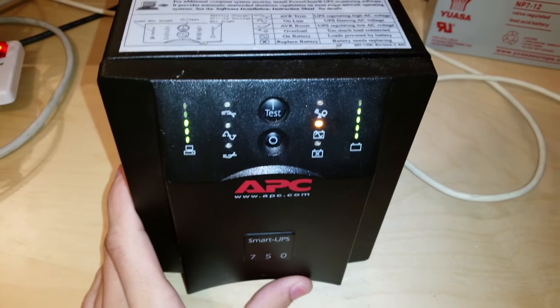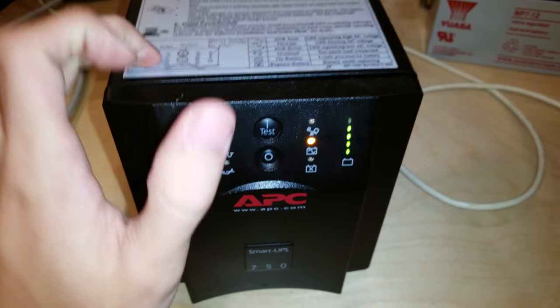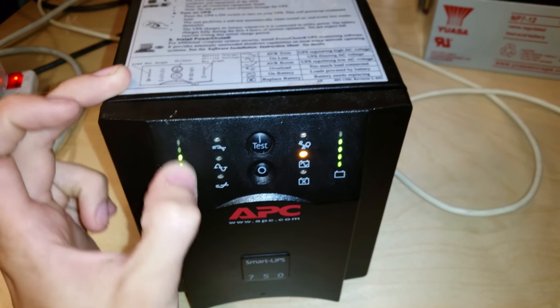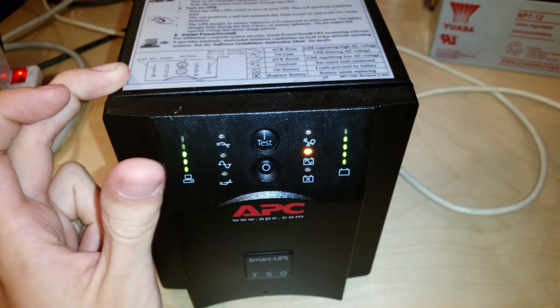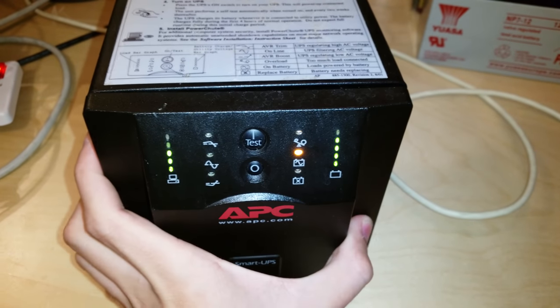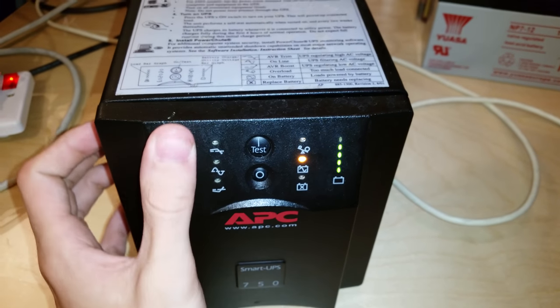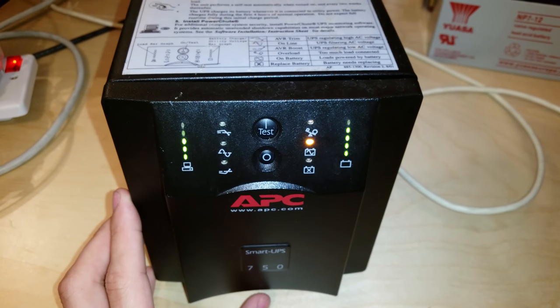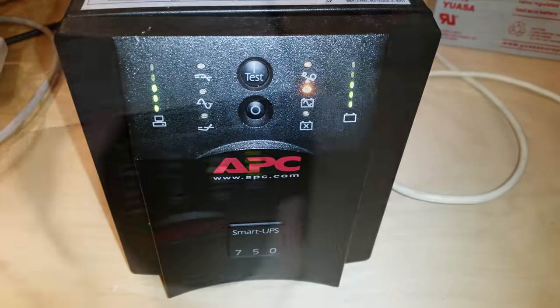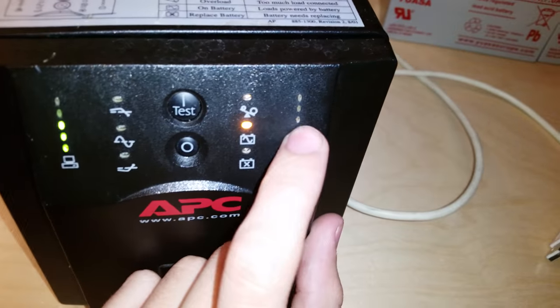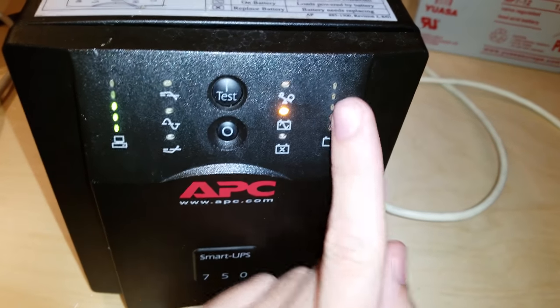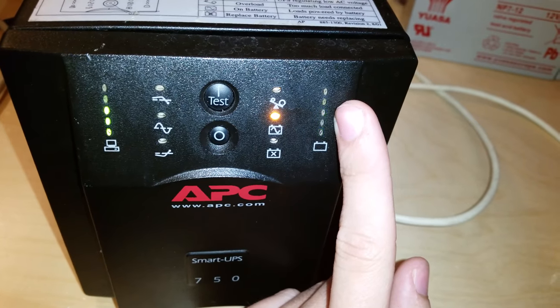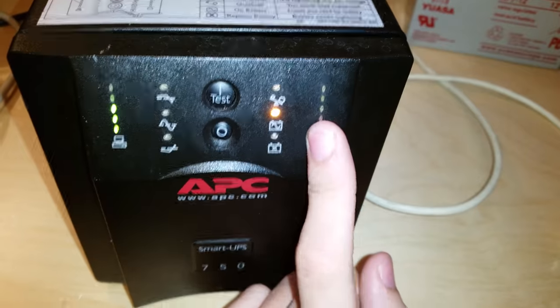That's the basic rundown of it. You just run the batteries completely flat so that then records how long it managed to run for this load that it's under now with like 60-ish percent. It's probably not going to be at that load all the time. The chances are the average load on this thing is going to be around about 40 to 50 percent, but it may hit as high as 60, which is why I'm calibrating it for a 60 percent load. Anyway, I'll come back as this does things. Okay, so it's now started beeping more, but as you can see it's still showing three bars here. This is because it's really not sure. It thinks it's got about half the battery left, but it also thinks it's likely to die. This is why you have to recalibrate these things.